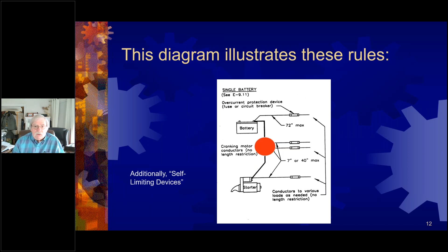With AC, there are some other rules. The 10-foot rule comes into play, and if the location of the main shore power disconnect circuit breaker is in excess of 3 meters, you're going to need an additional circuit breaker. And this gets very real as we see more and more boats with transom-mounted shore power inlets, and the main panel is forward in the boat somewhere. I mean, it's very easy to get to that 10-foot length. What most builders that find themselves in that situation are doing is putting the circuit breaker right next to the shore power inlet, and that works just great.